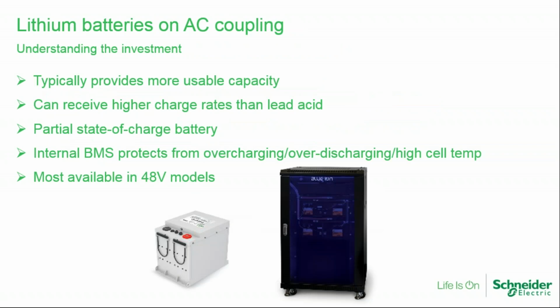With lithium batteries, they come out at 48 volts, and so they can do partial discharge. They can accept higher rates of charge, in some cases C over 1. So that's pretty good. Their internal BMSs can protect them fairly well. One of the worst things, though, with the BMSs is that if you exceed temperature, the battery will disconnect. Well, you don't want the inverter to see 0 volts, so you really need to be careful with making sure that the battery bank doesn't completely disconnect or shut off.